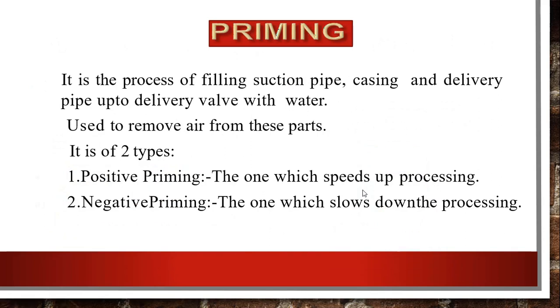Always remember: before starting a centrifugal pump, priming is very necessary. Priming is the process of filling the suction pipe, casing, and delivery pipe up to the delivery valve with water, so that the air pockets present inside the casing are removed and the efficiency of the pump is not affected. Priming is used to remove air from the parts. It is of two types: positive priming, which speeds up the process, and negative priming, which slows down the process.